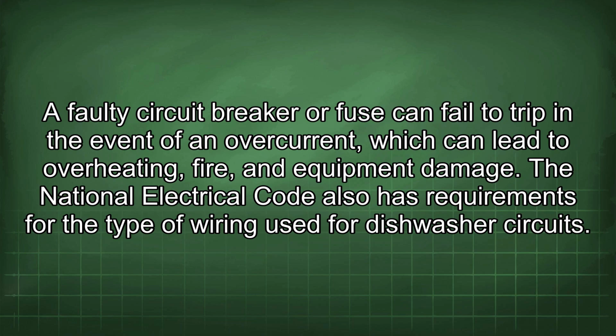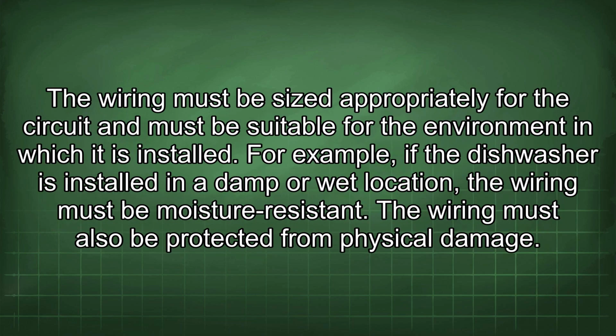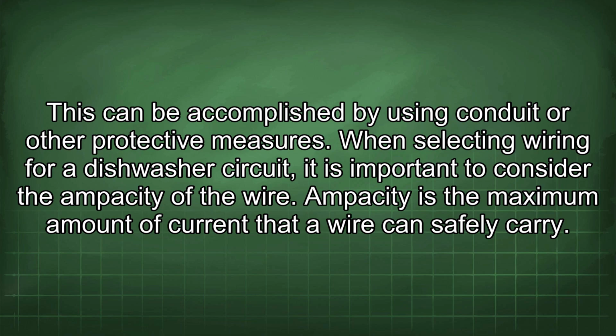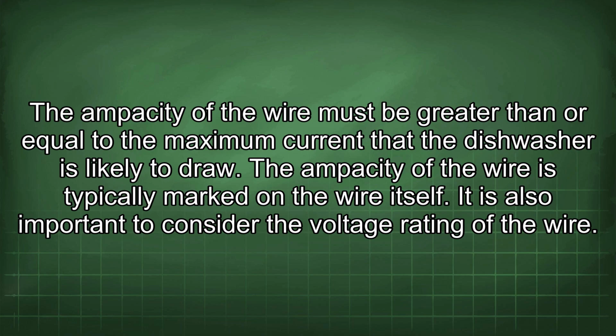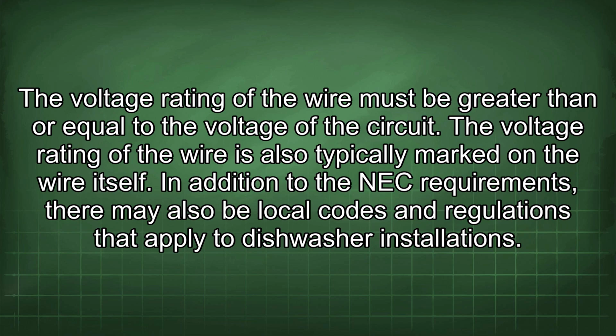The National Electrical Code also has requirements for the type of wiring used for dishwasher circuits. The wiring must be sized appropriately for the circuit and must be suitable for the environment in which it is installed. For example, if the dishwasher is installed in a damp or wet location, the wiring must be moisture resistant. The wiring must also be protected from physical damage. This can be accomplished by using conduit or other protective measures. When selecting wiring for a dishwasher circuit, it is important to consider the ampacity of the wire. Ampacity is the maximum amount of current that a wire can safely carry. The ampacity of the wire must be greater than or equal to the maximum current that the dishwasher is likely to draw. The ampacity of the wire is typically marked on the wire itself. It is also important to consider the voltage rating of the wire. The voltage rating of the wire must be greater than or equal to the voltage of the circuit. The voltage rating is also typically marked on the wire itself.